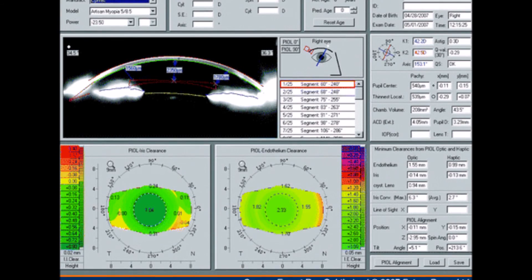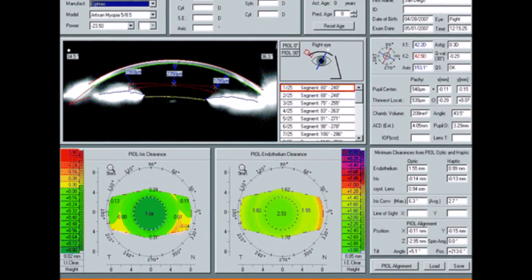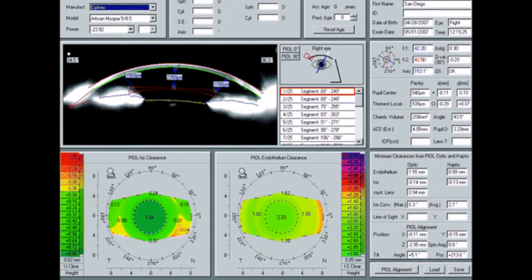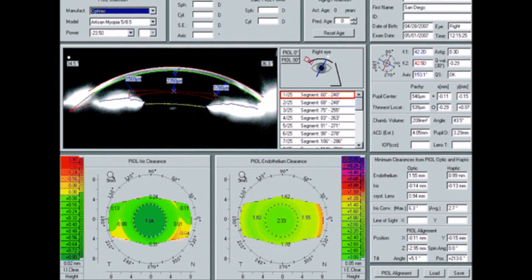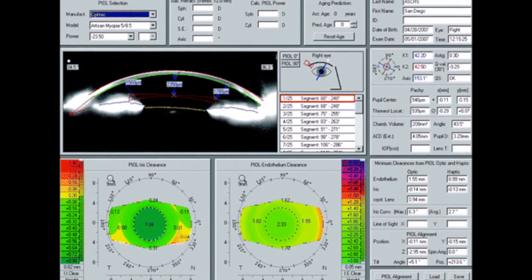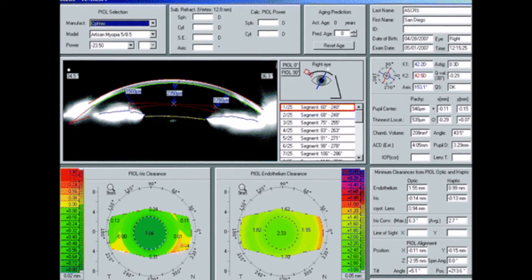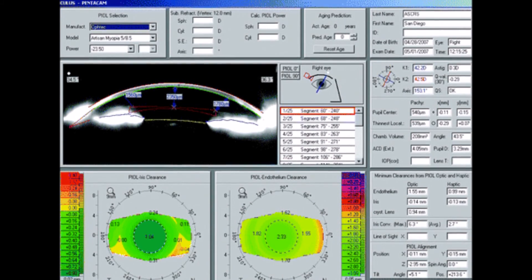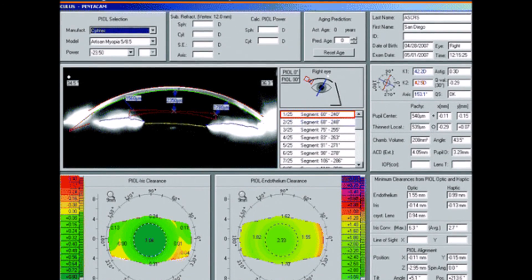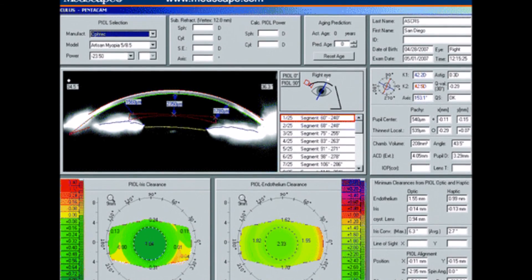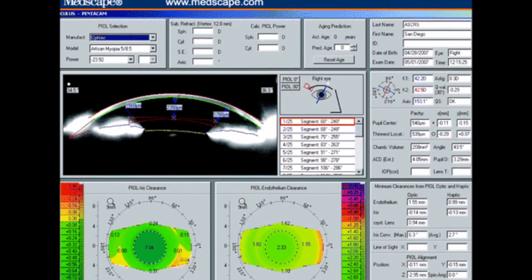Unfortunately, Scheimpflug imaging does not image the iridocorneal angle with much clarity as the blue light scatters at the scleral tissue. Consequently, structures at the angle and posterior to the iris are not optimally imaged. Other modalities such as ultrasound biomicroscopy are much better at imaging the iridocorneal angle.